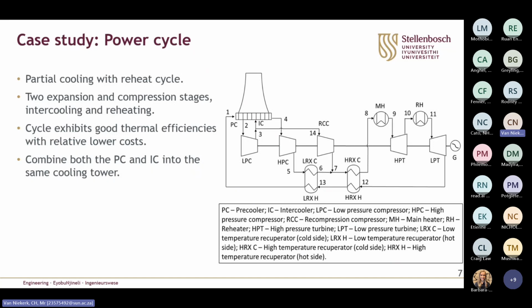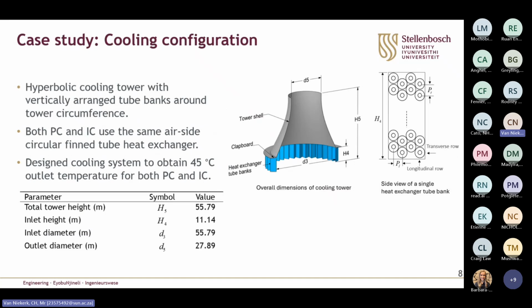power cycles, and we specifically consider the design and evaluation of a cooling system for a 50 megawatt partial cooling with reheat cycle. So this cycle features 2 expansion and compression stages with an intercooler and reheater, and we specifically chose this cycle due to its good balance between operating thermal efficiency and comparatively lower overall component costs in comparison to other cycle arrangements. And in this case, we also combined both the cooling heat exchangers, so that's the pre-cooler and the intercooler, into the same cooling tower configuration.